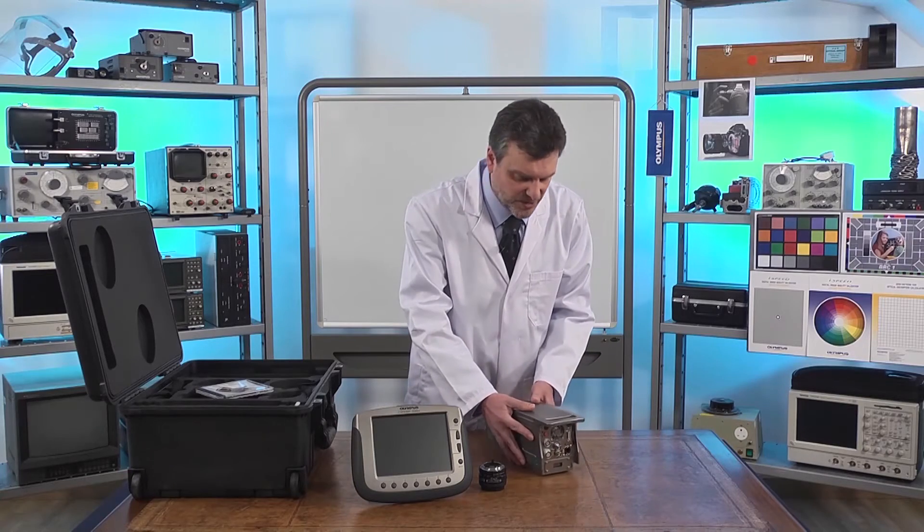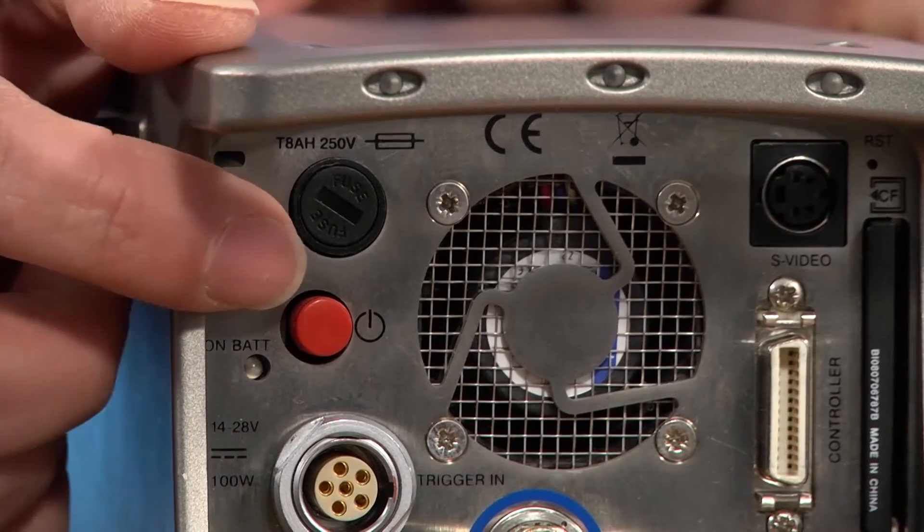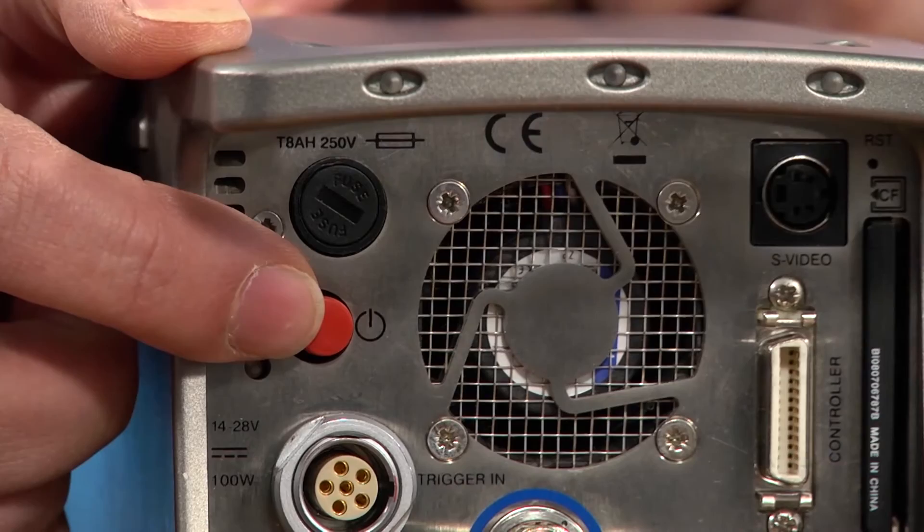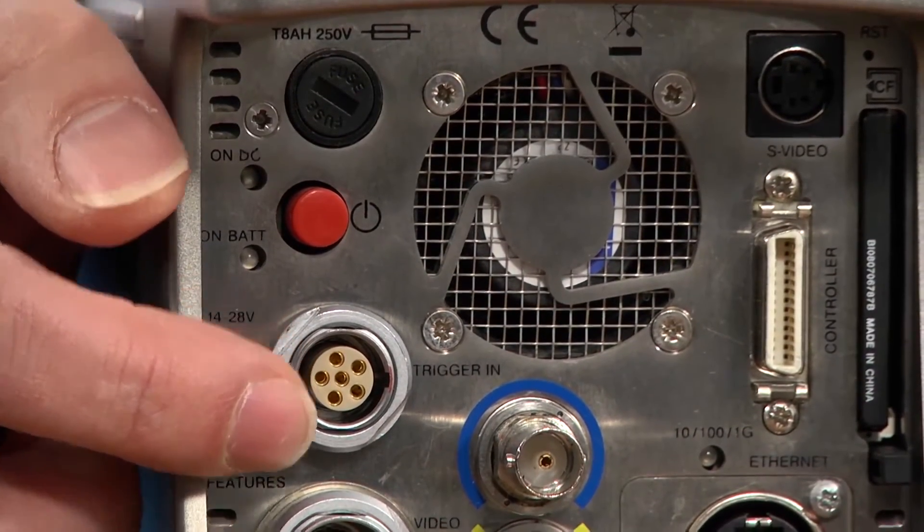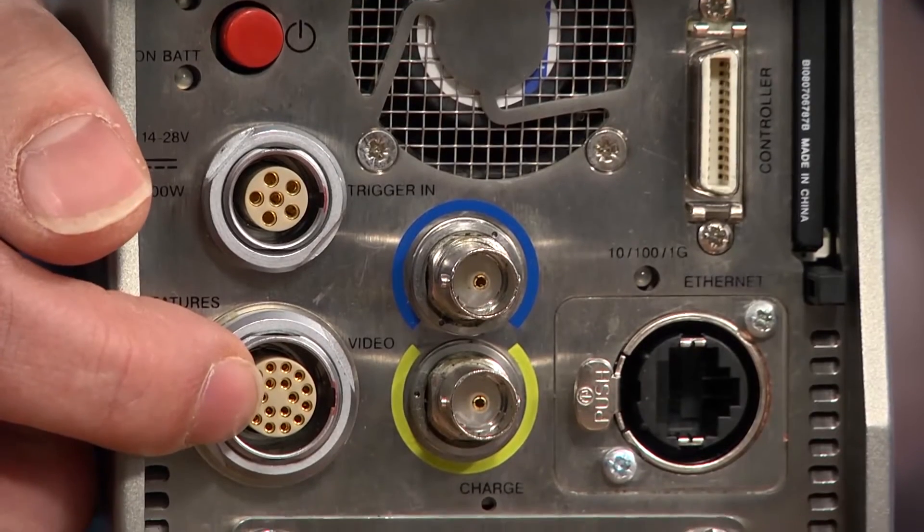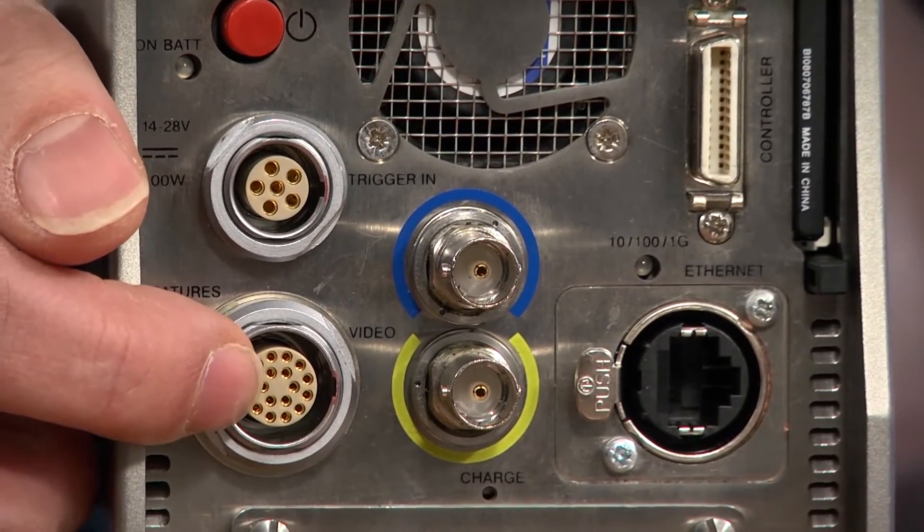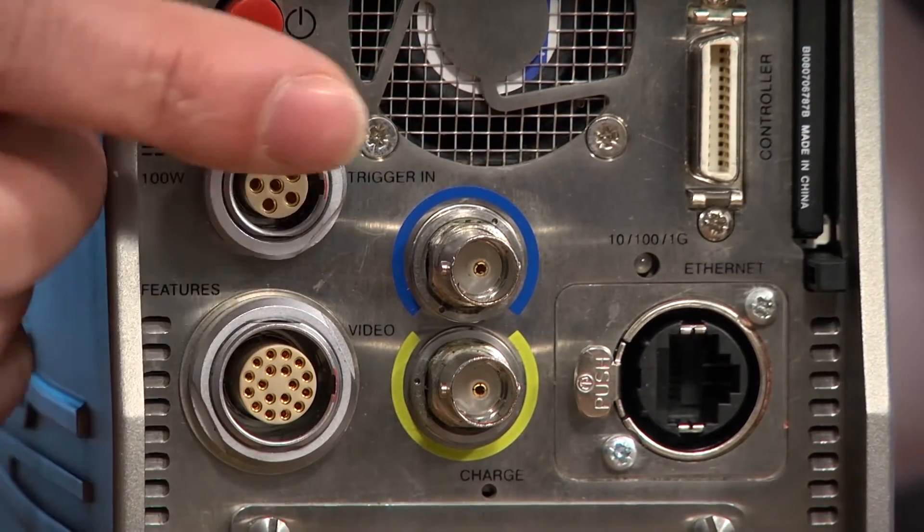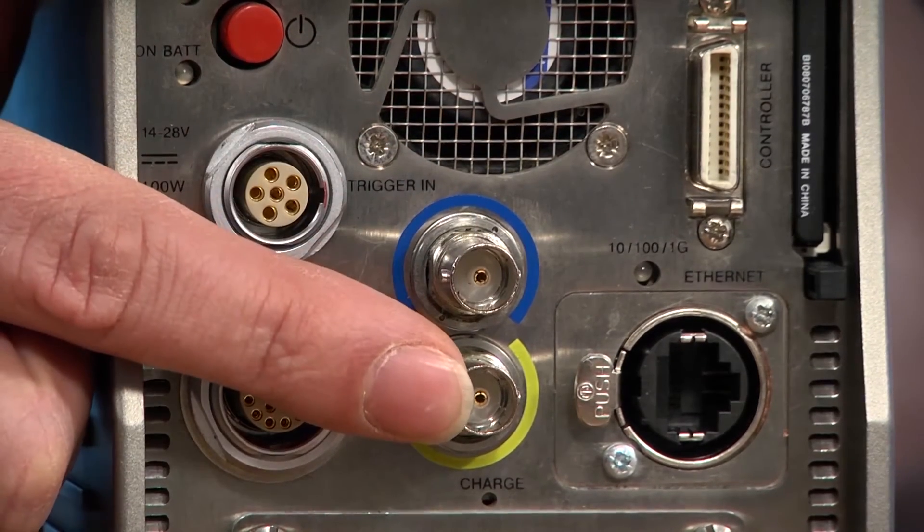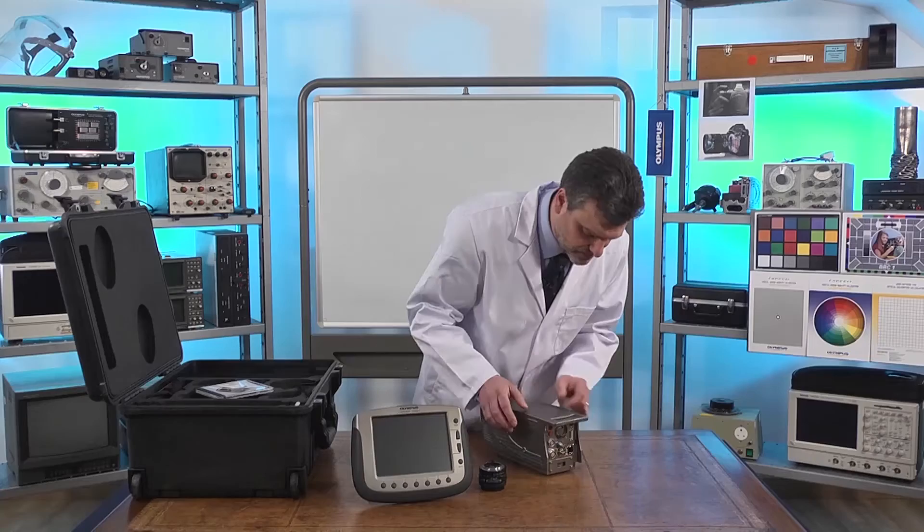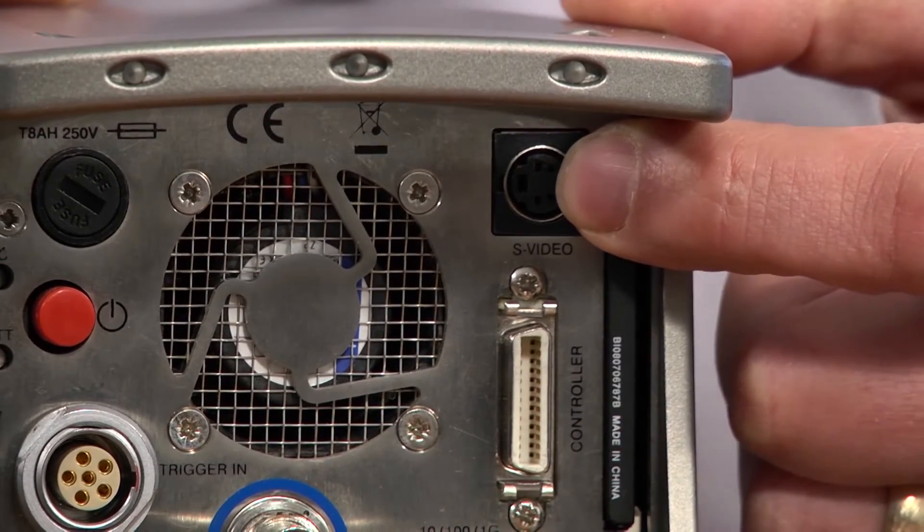If I rotate so you can see the back panel, over here we have the power switch, then there's the power input, then the feature connector with multiple trigger and sync inputs and outputs. The trigger input is on a BNC, we have a BNC video output, there's an S video output.